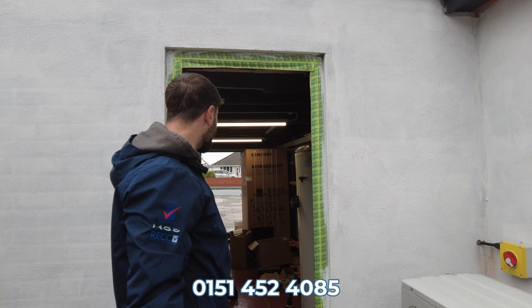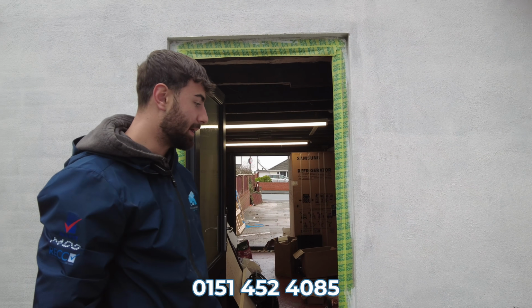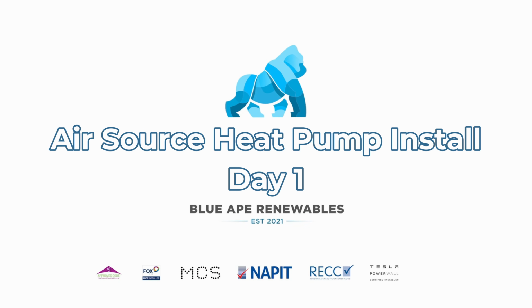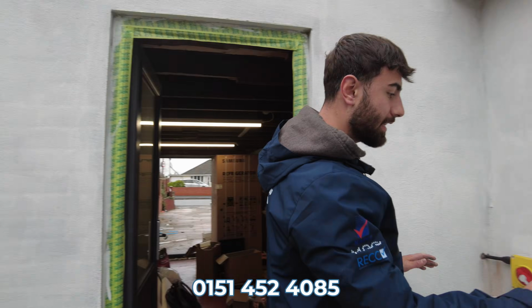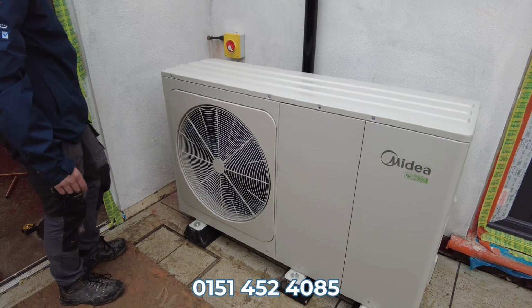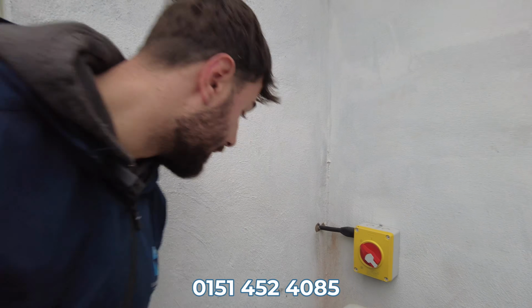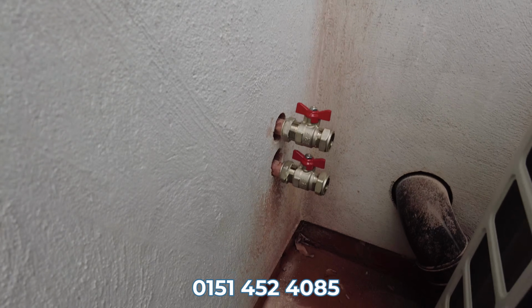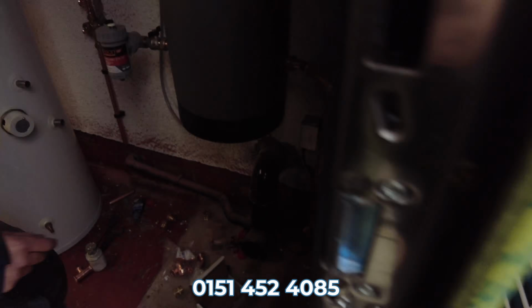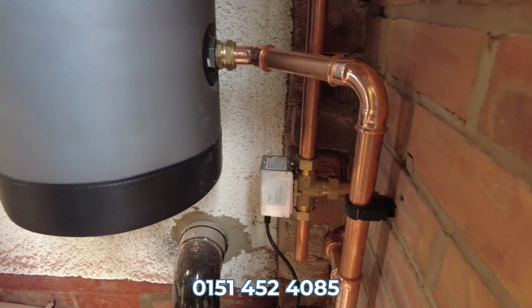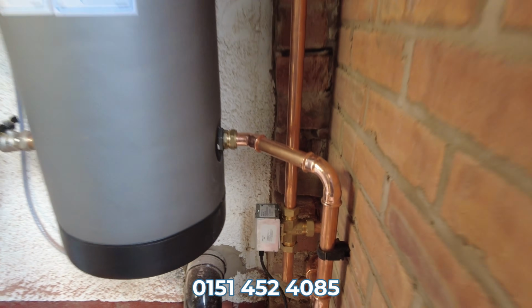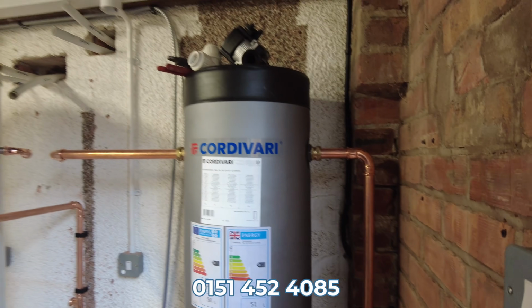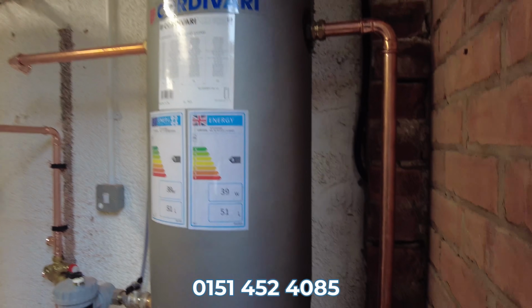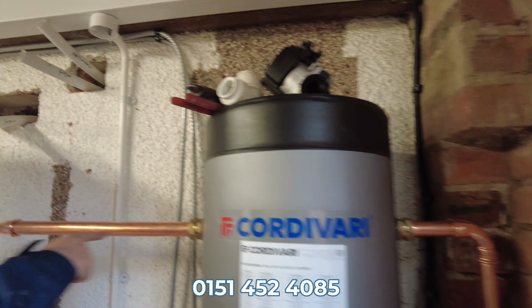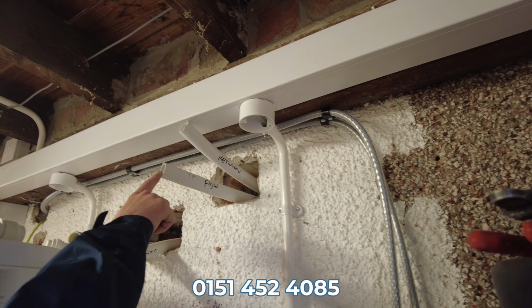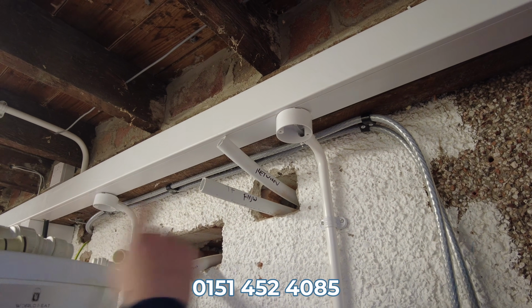Right, this morning when we got here, we didn't have anything to rip out, so it's a clean install. Getting the heat pump in place, measuring up where we are, and then out the back, we drilled through with 1.25 inches to 1.5 inches, fitting straight through out here into the 3-port valve, which connects to the top of the buffer. This comes from the heat pump, heats up the water in, then it will come out the top here and connect to the heating for upstairs, all your radiators and everything.